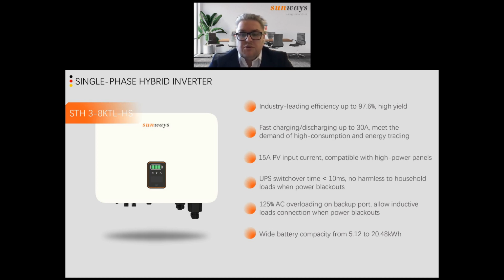And we use only high voltage batteries, even for single phase inverters. This is something also not so popular yet, but in our opinion, this allows to reduce cost of the system in the future. Also, it allows fast charging and discharging, and the system itself is more stable than with the low voltage batteries. So in here you can see that this is 30 amps charging and discharging power, and you can connect the battery size from 5 to 20 kilowatt hours.